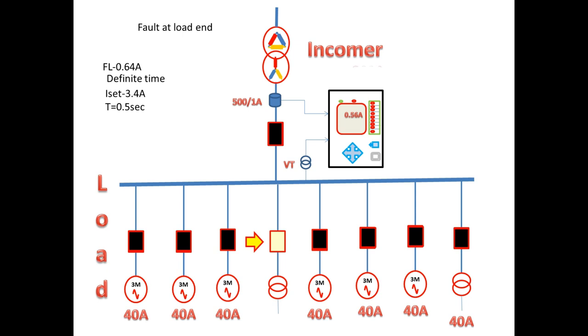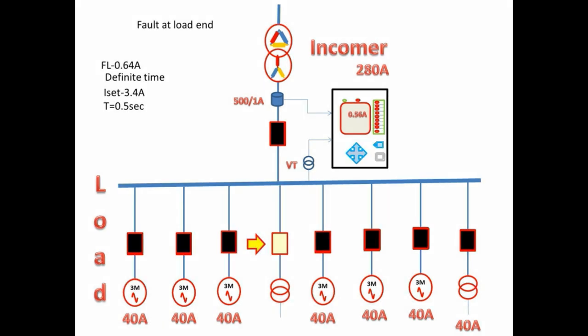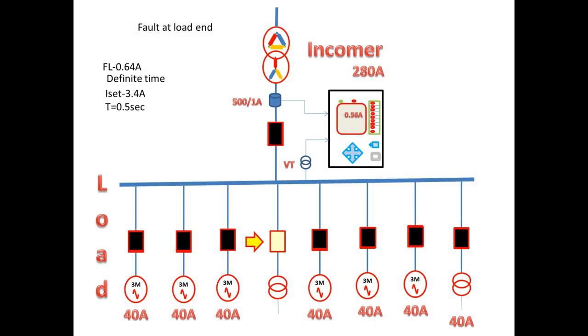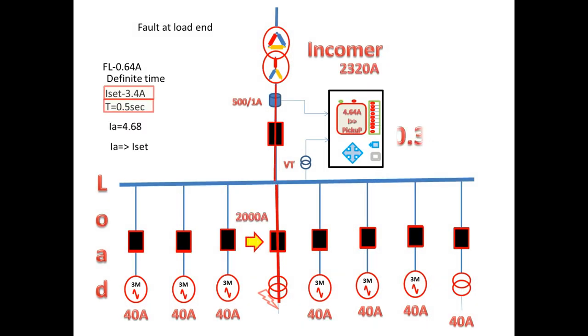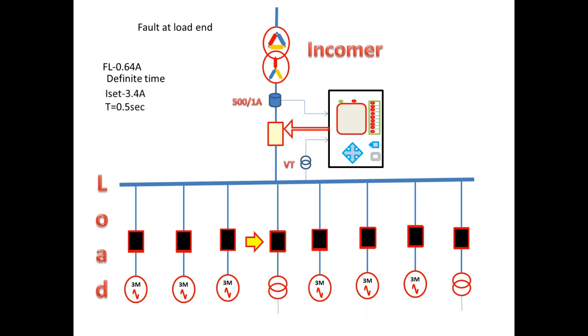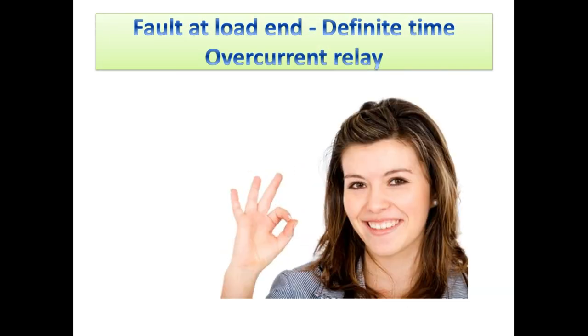Within this time, if the outgoing feeder trips, the incoming current will get reduced and it will remain in service. So all other loads will get power supply. In the other case, if the outgoing feeder fails to trip, the incomer will take the chance and trip the breaker. The fault isolation time is only 0.5 seconds — a lesser time for isolating a fault at load end. So for this type of fault we can choose definite time.